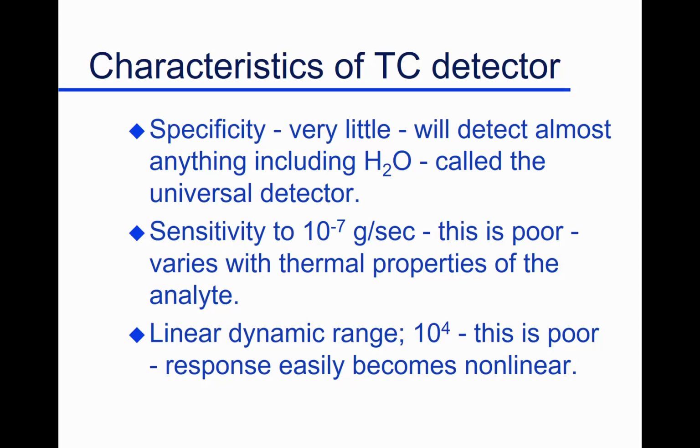Specificity, very little specificity. You'll get a response from anything, any compound, water, gas, whatever that's going through that column, because you change the heat transfer. So the only thing it won't detect is the carrier gas, the mobile phase. If you would put more helium in there, it wouldn't detect it, if helium's the carrier gas, but it'll detect anything else. That's the beauty of it. It's called the universal detector. You don't get it without paying for it in some other way.